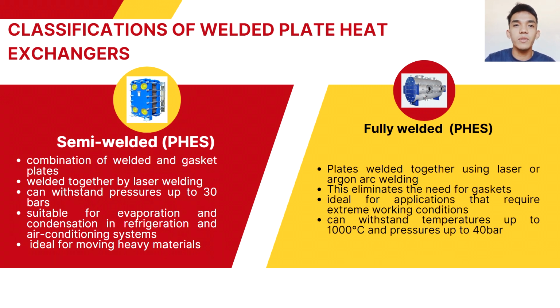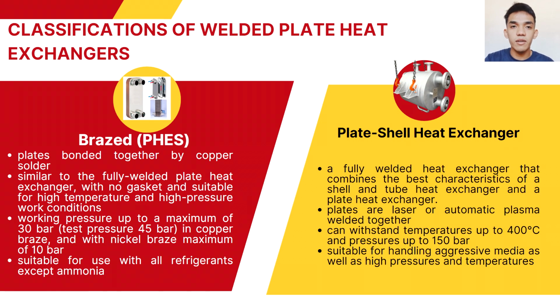So, fully welded can withstand temperatures up to 1000 degrees Celsius and pressures up to 40 bar, and are also capable of handling highly aggressive or corrosive fluids. However, the number of plates in the fully welded plate heat exchangers cannot be adjusted to meet the varying heat load requirements, and they can only be cleaned using chemical cleaning methods. Next is the brazed plate heat exchangers.